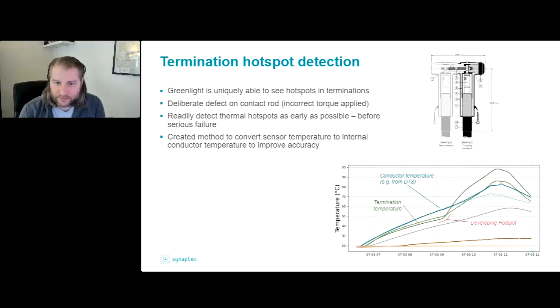The contact rod inside the termination had the wrong torque applied, so it effectively wasn't installed correctly. That worked in the sense that it created a hotspot that developed in the termination, and our point temperature sensing was able to see it immediately - that's the kind of knee point you can see on the plot here. This is because our sensor is placed directly on the termination, as close as possible to that contact point.